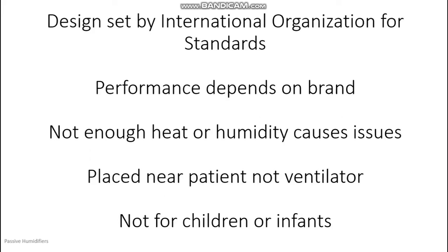Details of HMEs include design set by International Organization for Standards. Performance depends on brand. Not enough heat or humidity causes issues. Placed near patient, not ventilator. Not for children or infants.